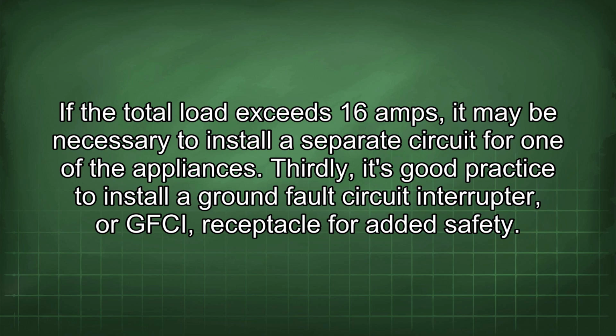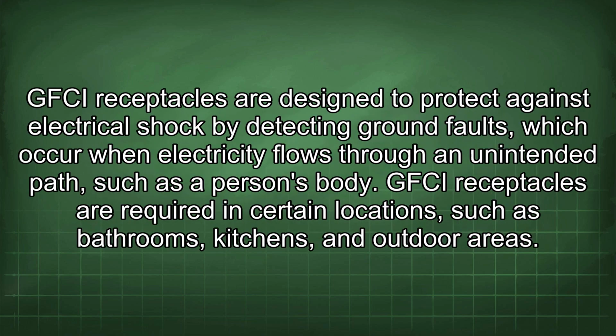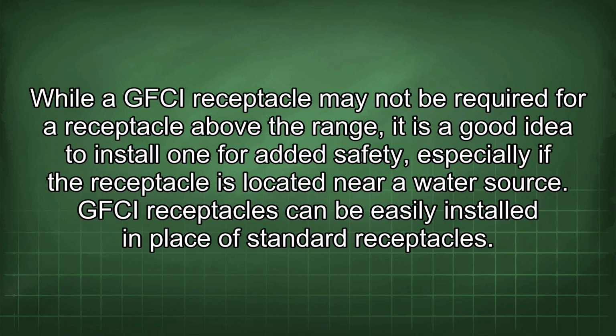of the appliances. Thirdly, it's good practice to install a ground fault circuit interrupter, or GFCI, receptacle for added safety. GFCI receptacles are designed to protect against electrical shock by detecting ground faults, which occur when electricity flows through an unintended path, such as a person's body. GFCI receptacles are required in certain locations, such as bathrooms, kitchens, and outdoor areas. While a GFCI receptacle may not be required for a receptacle above the range, it is a good idea to install one for added safety, especially if the receptacle is located near a water source. GFCI receptacles can be easily installed in place of standard receptacles.